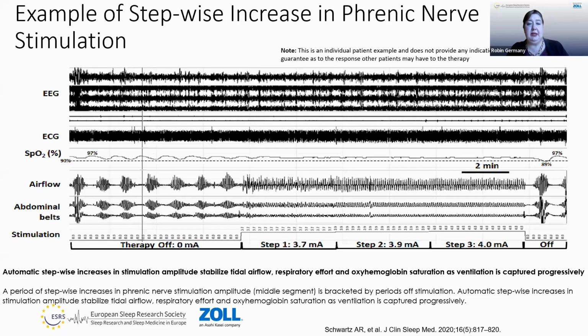It will begin the stimulation at a set minimum level, which you can see here is 3.7 milliamps. Then the device is going to look to see if the patient is breathing at that set respiratory rate. If the patient is not, and if you look at the airflow signal, I think in this example that's the easiest place to see this, you can see that breathing is not completely regular. Then the device is going to increase the stimulation, so here to 3.9, and it's going to look again. To my eye at 3.9, things look fairly stable, but the device actually says, no, you're not quite stable, and it walks it on up to 4.